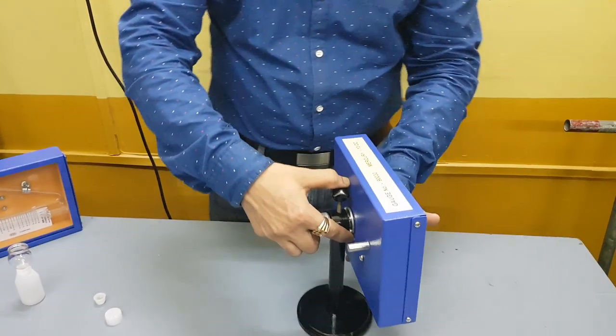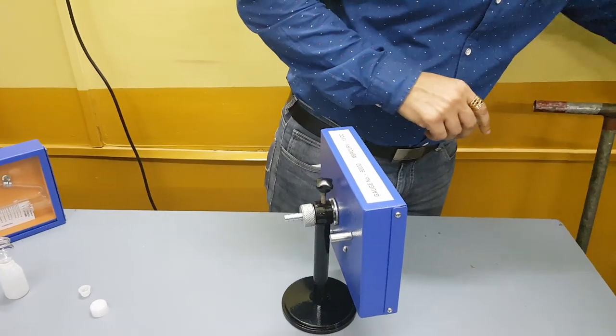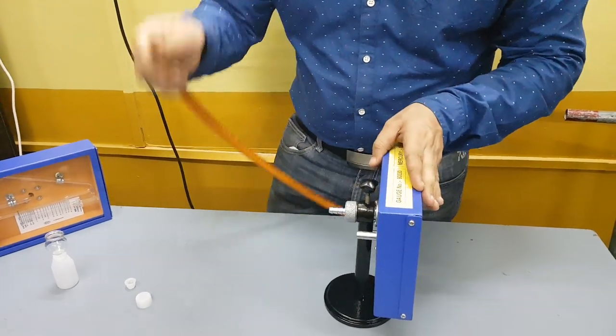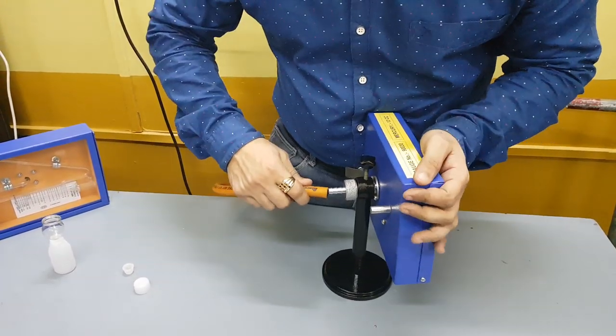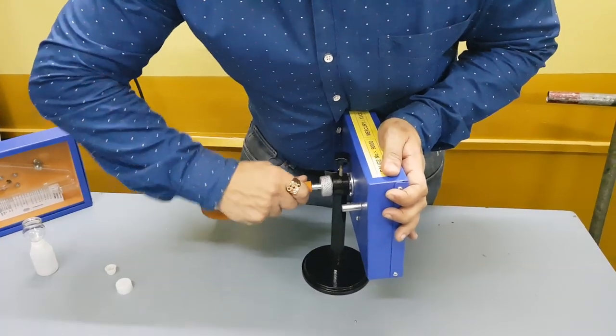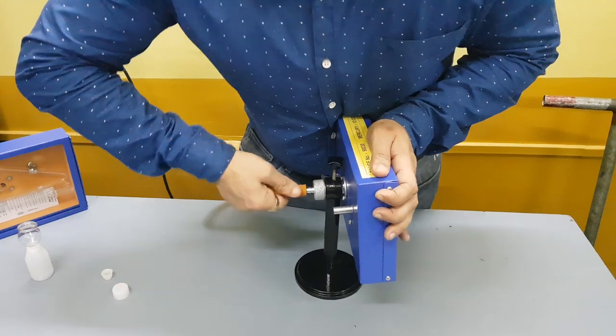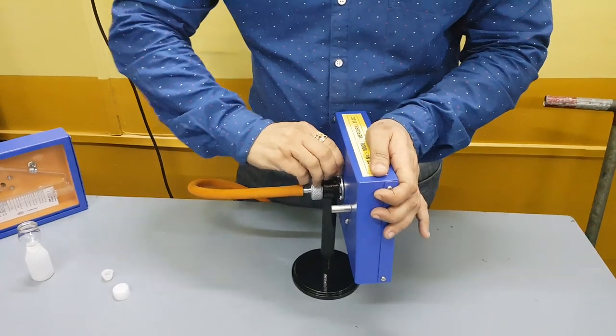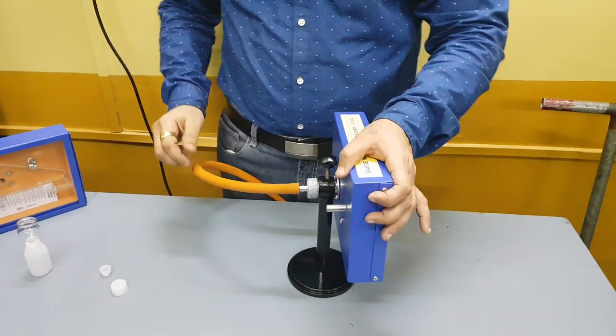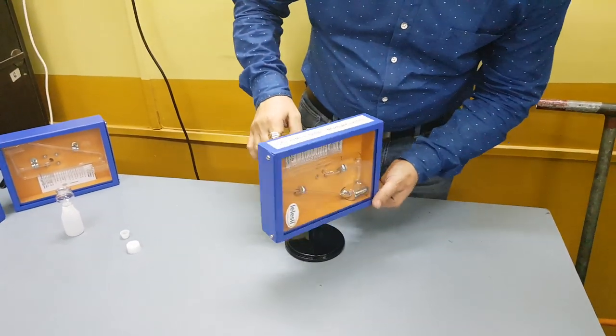Connect the vacuum in the same position, keep the nut locked. Now we are going to demonstrate how the tube has to be inserted onto the nipple. Always ensure that the left hand is supporting the gauge, rotate it in such a way that it at least climbs a single serration. Connect it, close the nut, start the vacuum, rotate the gauge.